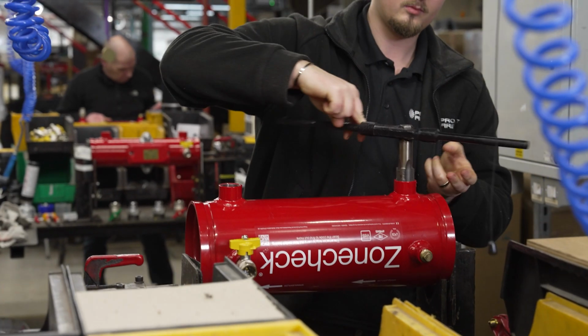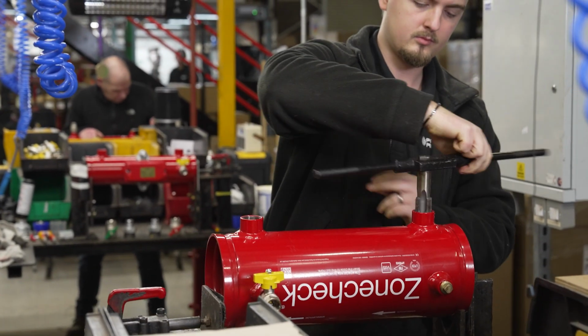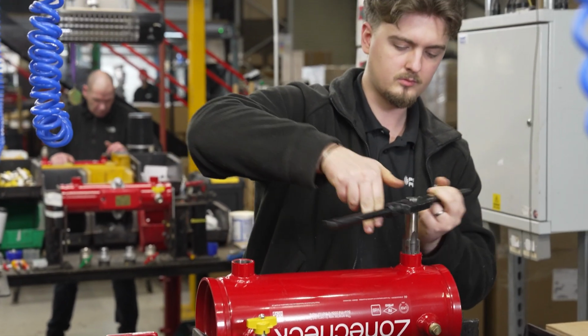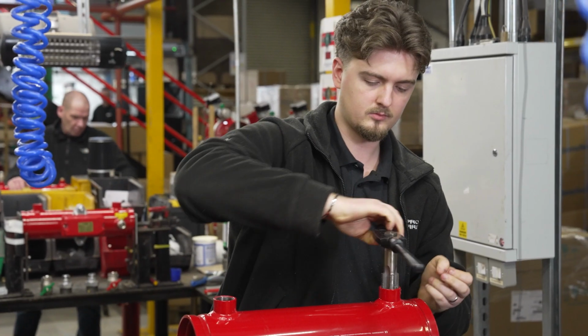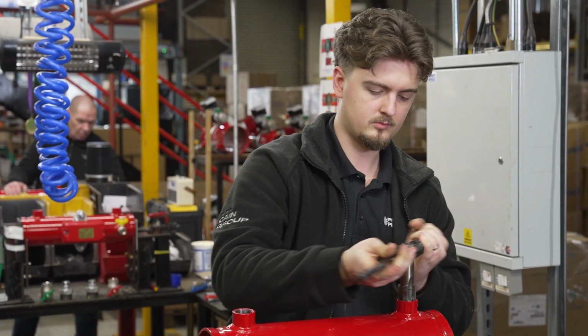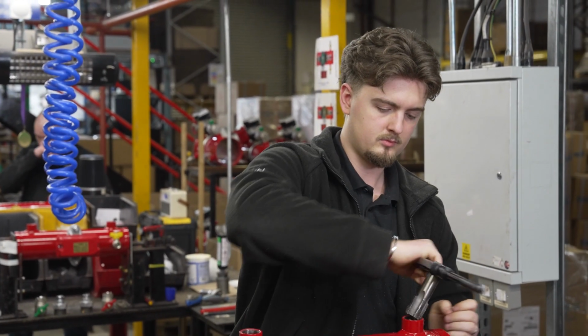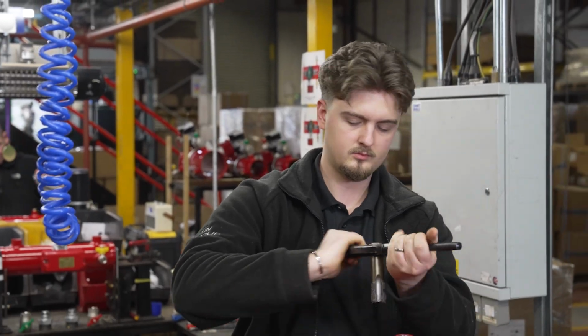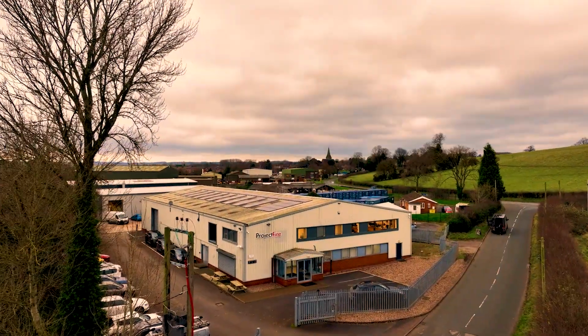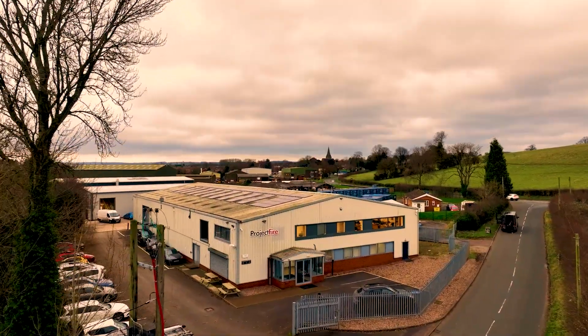Zonecheck is the original automated flow switch testing device manufactured in the UK by Project Fire Products Limited for over 25 years. If Zonecheck is correctly wired and installed, it usually works straight away. However, sometimes a few extra steps or checks are required to get the unit working, especially if the product has been left for an extended period of time without use.